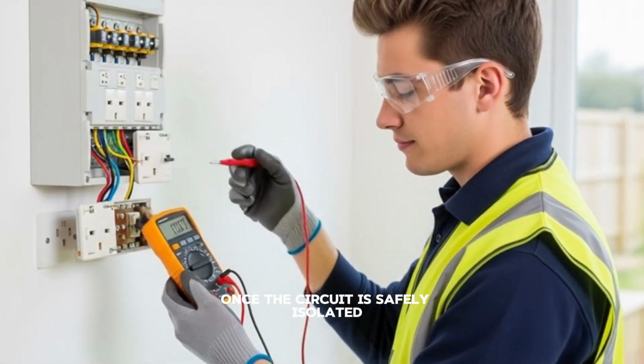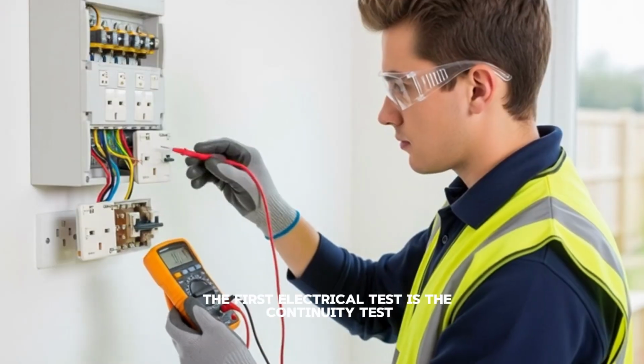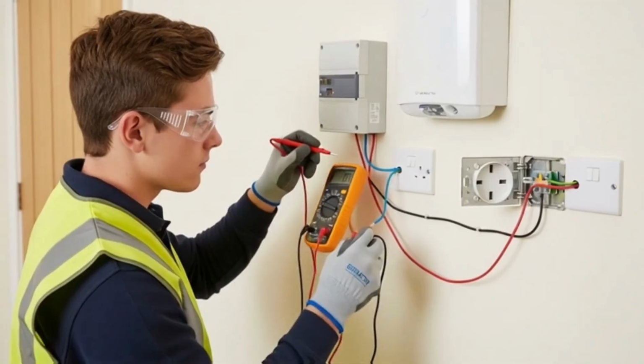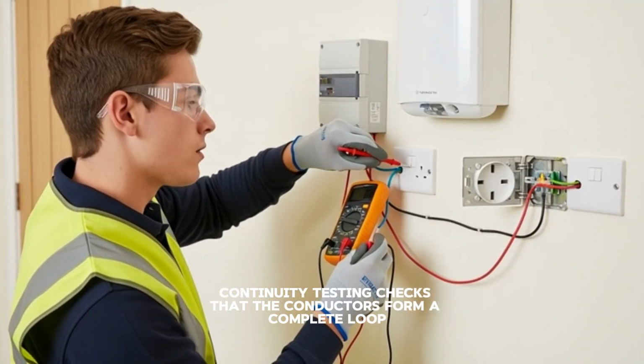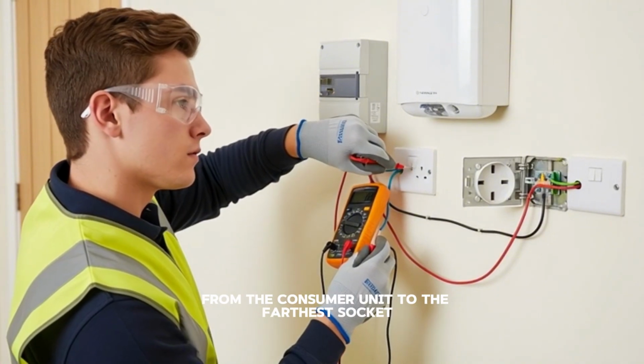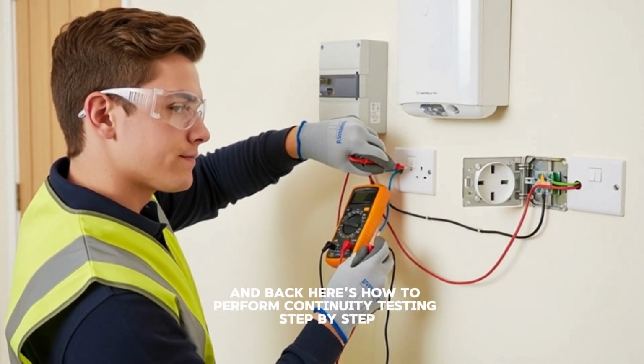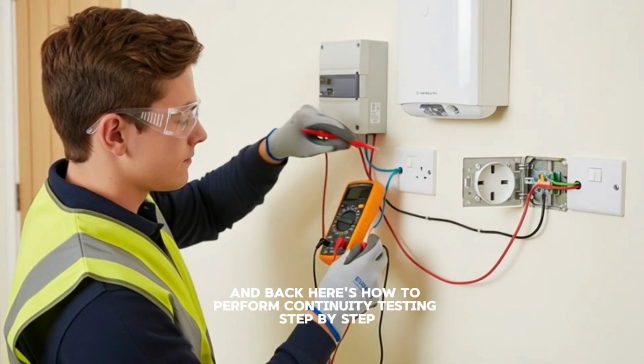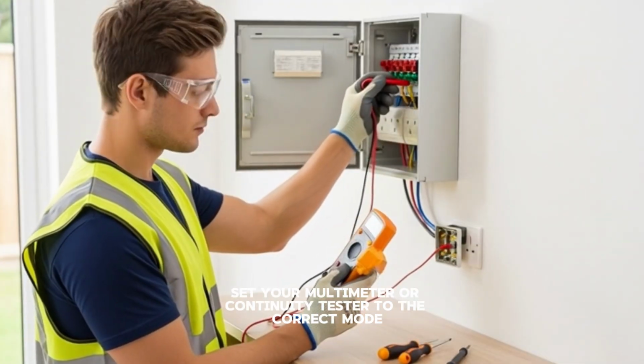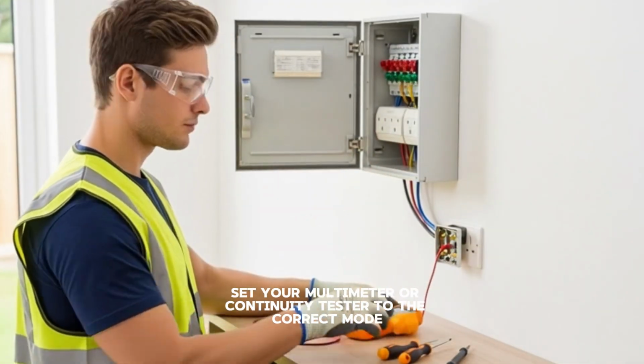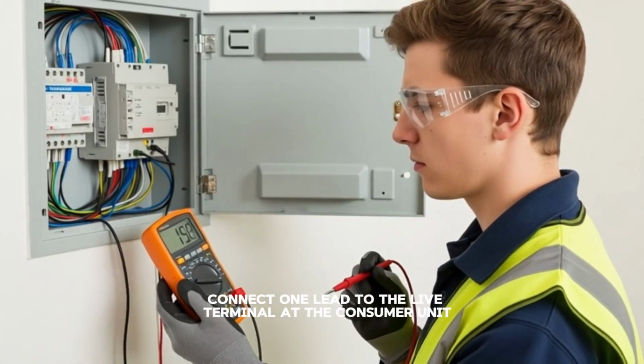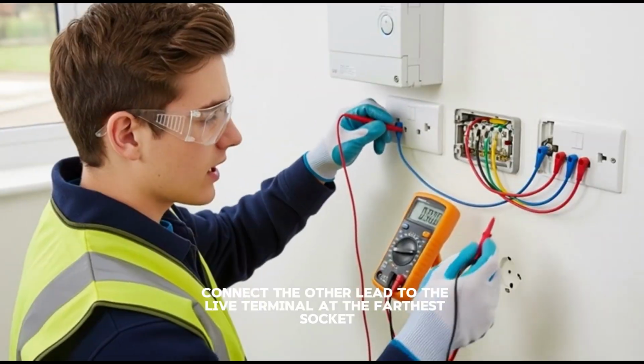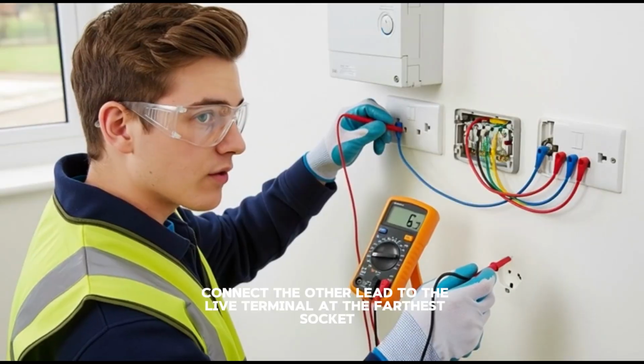Step 3. Continuity testing. Once the circuit is safely isolated, the first electrical test is the continuity test. Continuity testing checks that the conductors form a complete loop from the consumer unit to the farthest socket and back. Here's how to perform continuity testing step by step. Set your multimeter or continuity tester to the correct mode. Connect one lead to the live terminal at the consumer unit. Connect the other lead to the live terminal at the farthest socket in the ring.